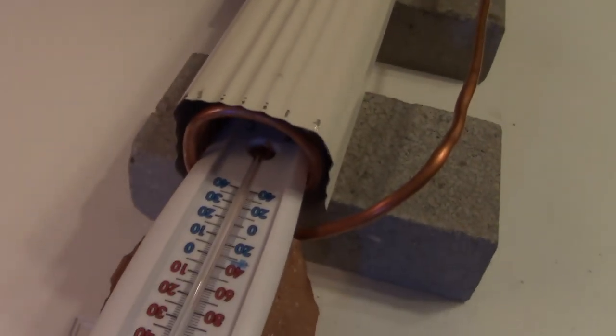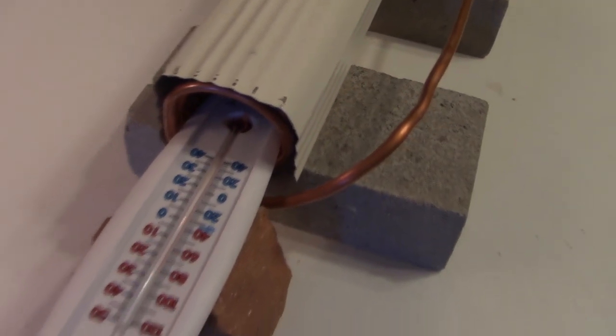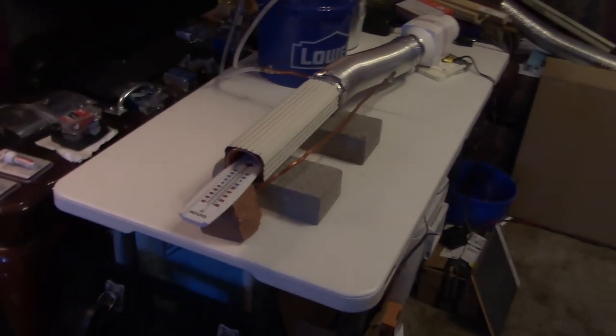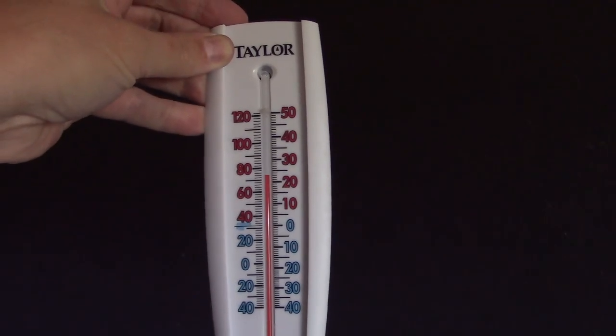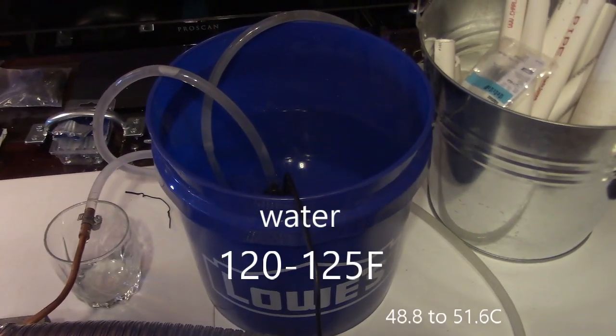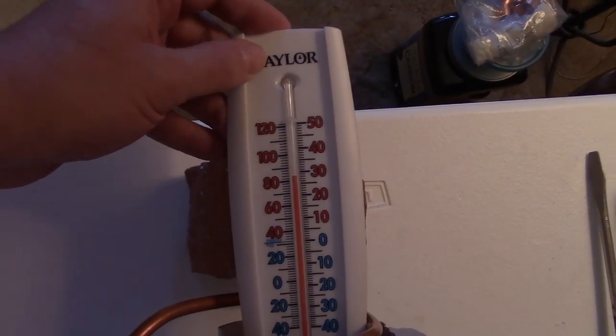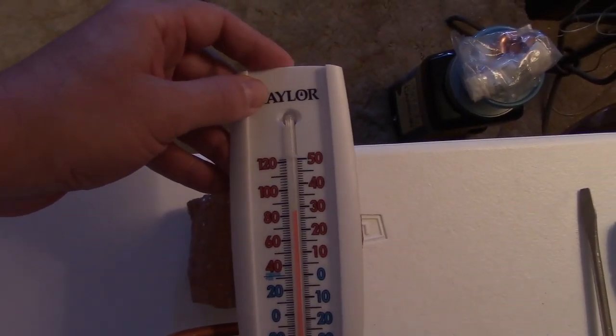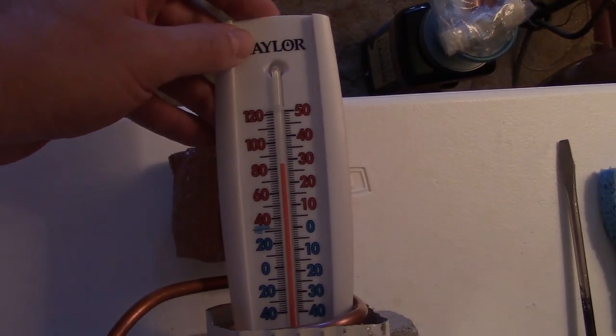The bulb of the thermometer is right in the middle so it's not touching the copper — it'll be a perfect shot on the air. Let's fire it up. Here's the air temp: about 85°F — went up 10 degrees. That's with pretty strong airflow though; we can slow that down a little.